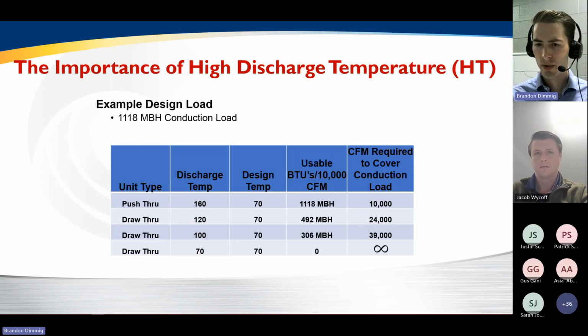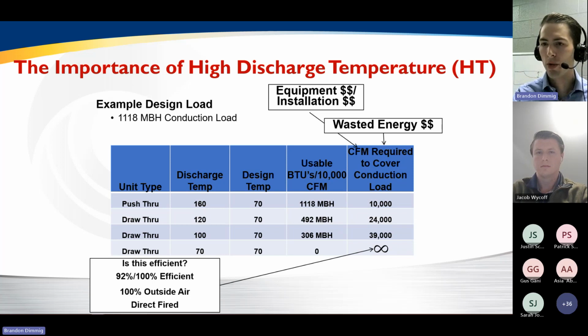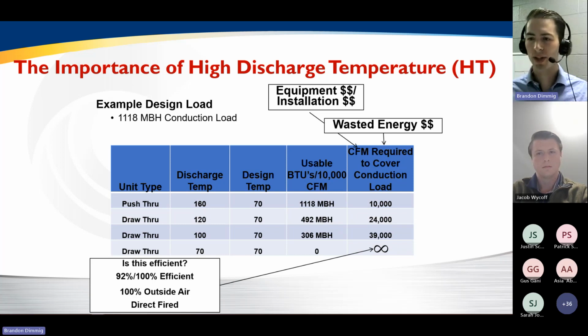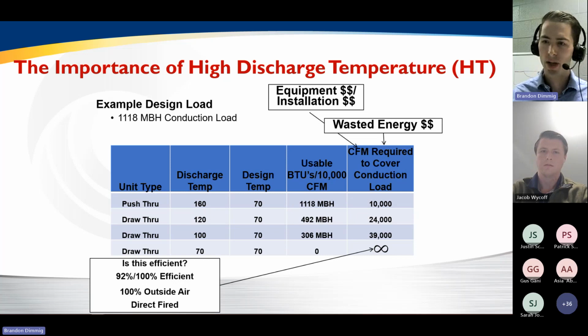And of course, if you take this to its logical end, if you don't have any temp rise at all above the internal temperature, you simply can't meet the conduction load. You've only heated the air load. And frankly, you've increased the air load considerably and just wasted energy because you're doing it in excess. So practically, whenever you increase the airflow of the unit, it's a bigger unit, bigger motors, more difficult install. And so you end up wasting energy and wasting money on units that don't need to be that large.